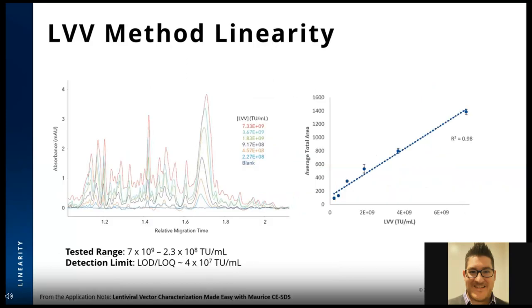We next explored the LVV CESDS method linearity. An LVV sample was serially diluted from 7×10⁹ TU/mL down to 2.3×10⁸ TU/mL and analyzed on Maurice to establish linearity and limit of detection. Nearly all LVV proteins are detectable across the entire dilution range. The LOD was calculated as three times the standard deviation of the response divided by the slope of the calibration curve, and the LOQ using 10 times the standard deviation divided by the slope. The LOD and LOQ values are both close to 4×10⁷ TU/mL, with an R-squared of 0.98. The LVV CESDS method is highly reproducible and responsive over a wide dilution range.